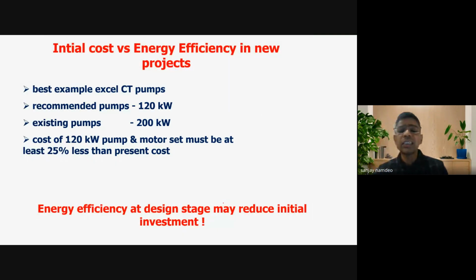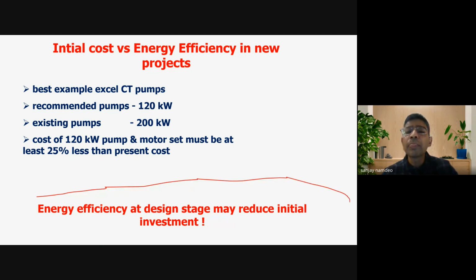So there is another example. Now there is another perception: that energy efficiency at design stage would cost us more. Very simple, let us say there's an efficiency class 1 equipment and an efficiency class 2 equipment. So our general perception is what? Efficiency class 2 equipment would be costly, right? But it is not true if we really select the proper size of the equipment.